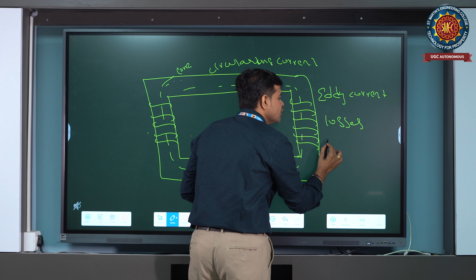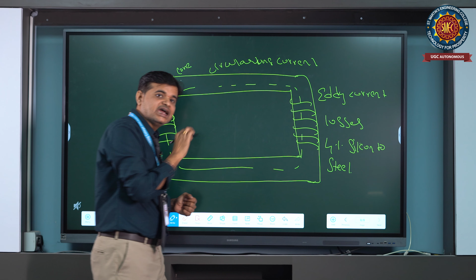This transformer core is generally made of silicon steel. We can reduce the eddy current losses by adding 3 to 4% of silicon to the steel. Why do we add it? It reduces the conductivity of the steel, and so we can reduce the eddy current losses. Again, up to some extent we can reduce the losses further.